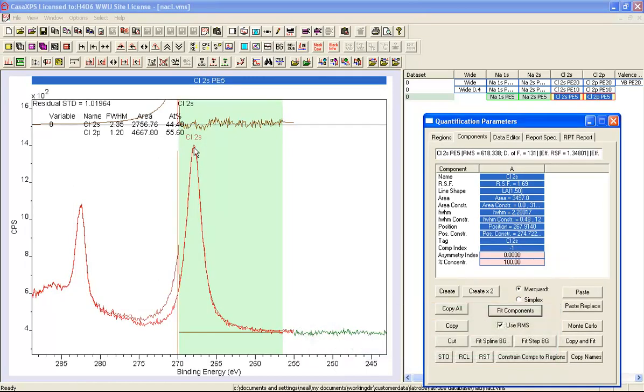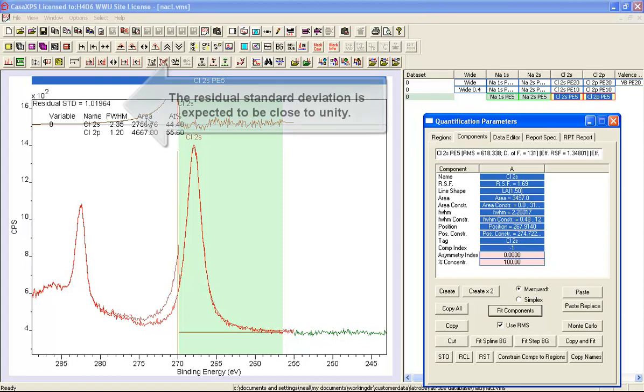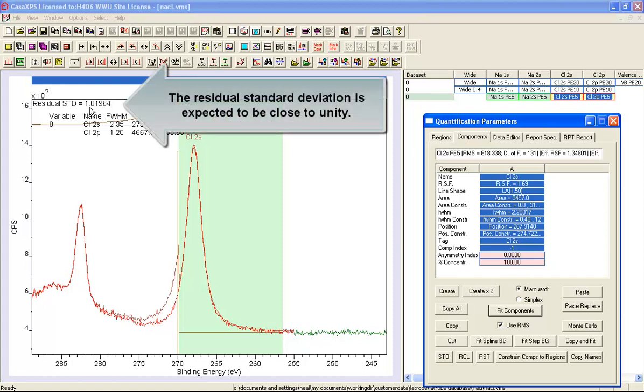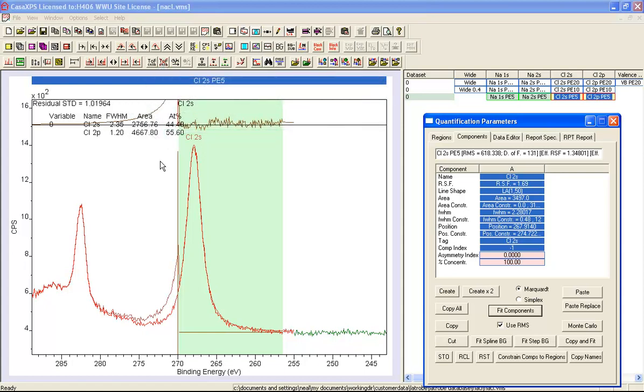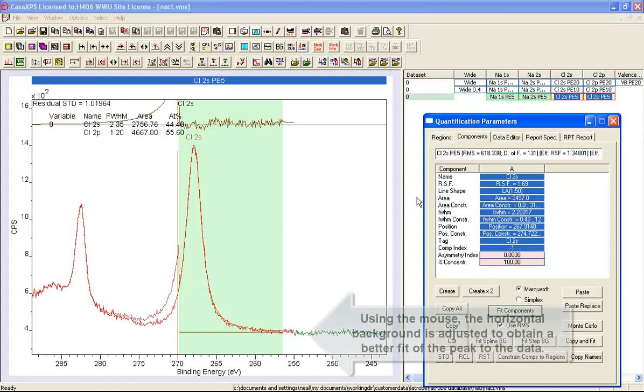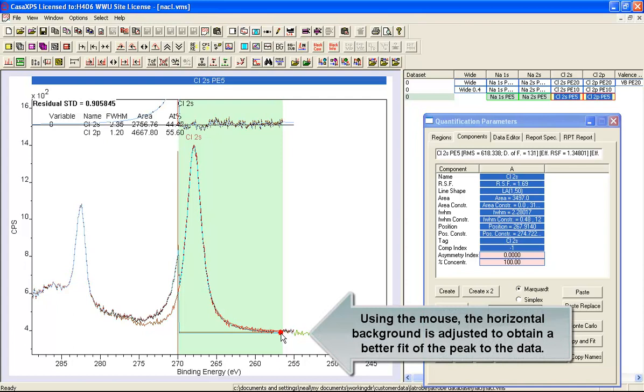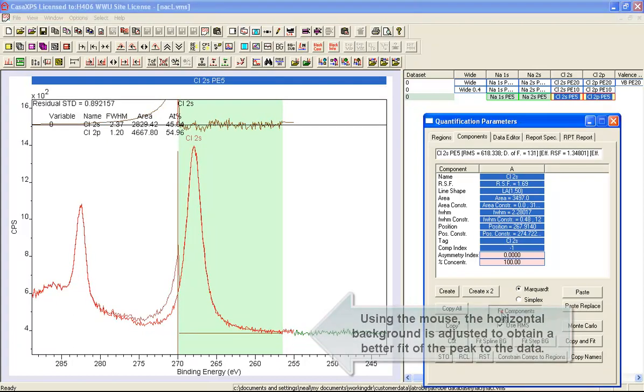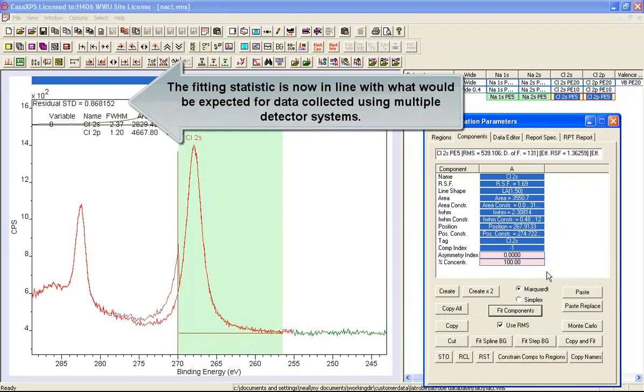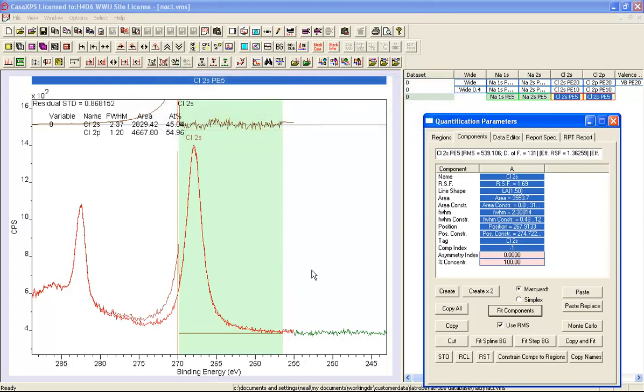When I say fit here, you can see that you get quite a good fit to the data. It's somewhere close to one which is what you'd expect for Poisson statistics. It's probably not quite as good as you can get because these data were collected using multiple detectors and they tend to give you a slightly over smoothed version of the noise signal to noise. What I'm going to do now is just make a little adjustment here. That dialogue window is coming up because I've got two spectra overlaid in this active tile and it is possible to fit to a set of spectra that are overlaid in the active tile but we're not interested in that.